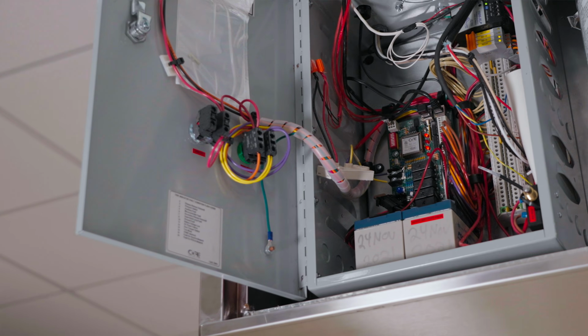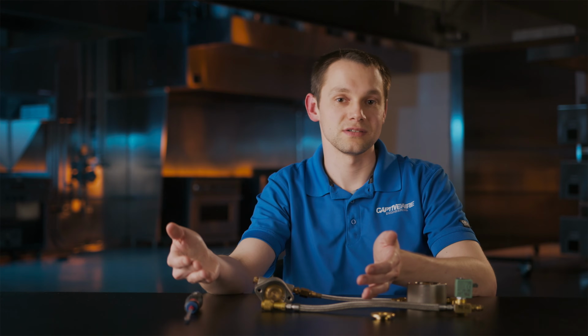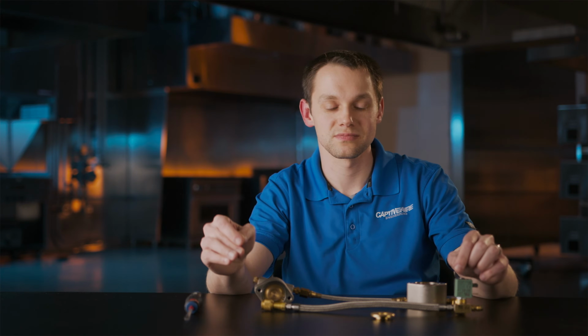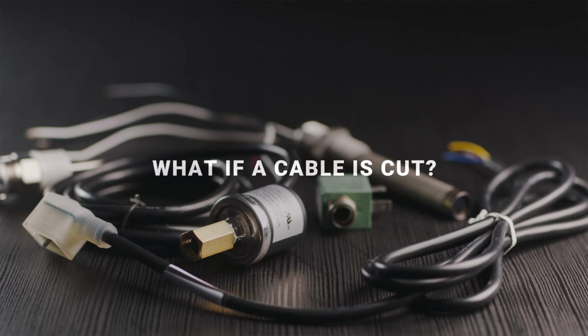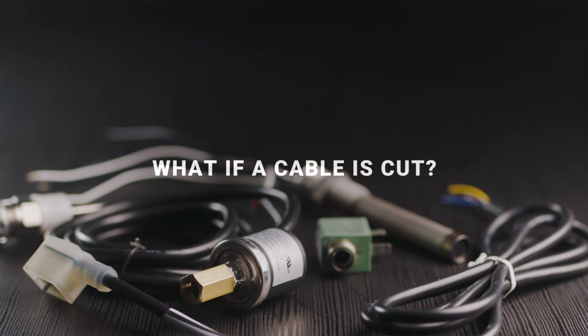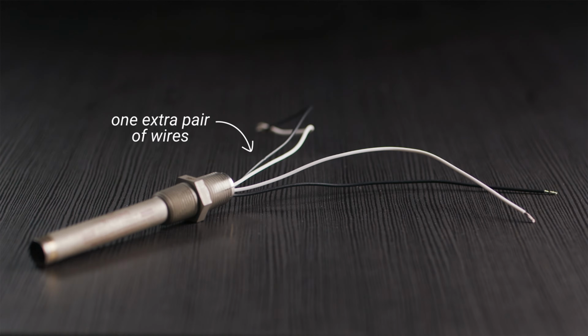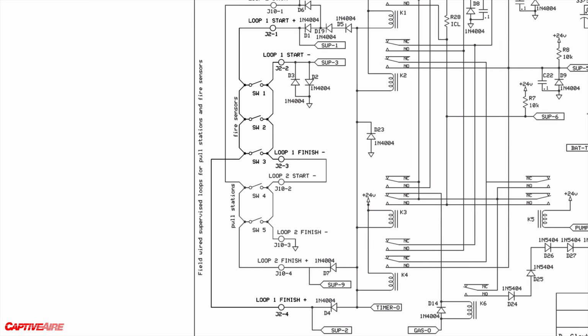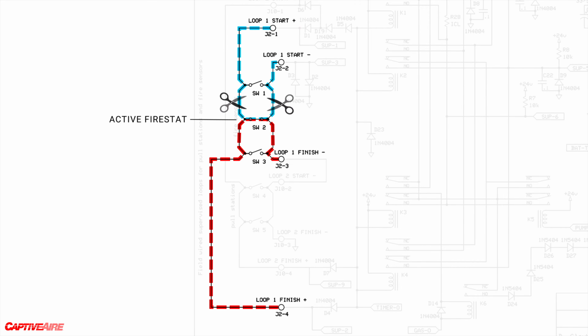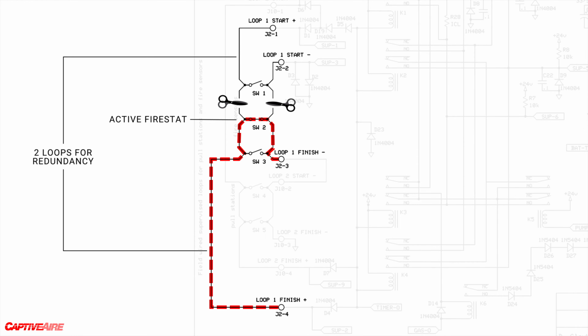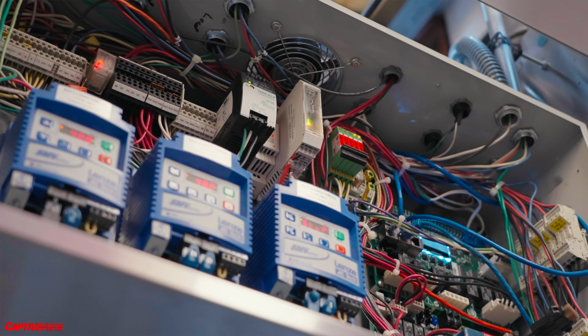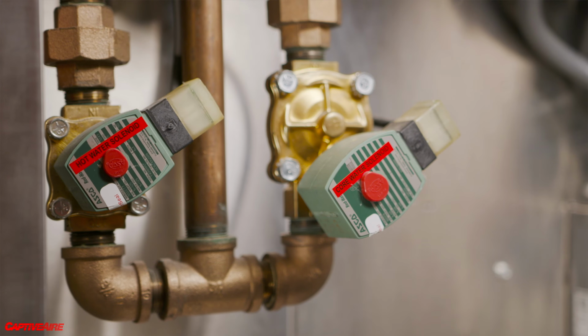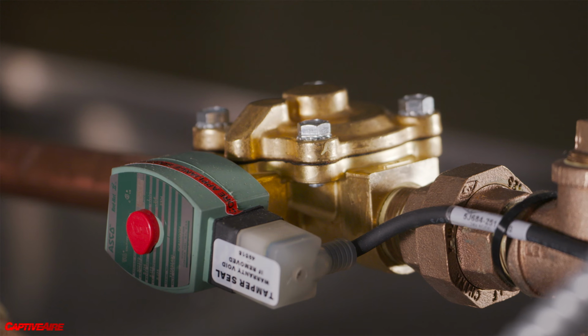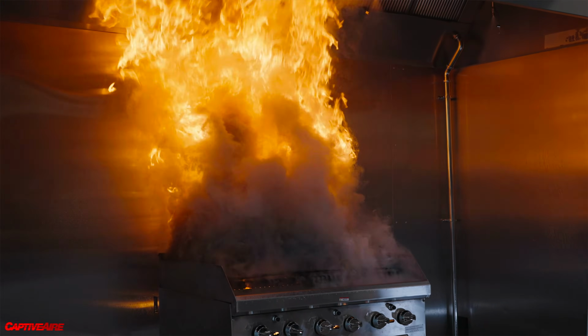The reality is we do have a battery backup system that even if there is a power outage, we'll have full capability of actuating that system and having everything safe. Okay, then what happens if a cable is accidentally cut or a component is faulty? With our fire stat, we implement a pair of redundant wires, and if you have fusible links, you just have one shot. If it breaks, it's literally not working. But even with our fire stat, if you cut up to 2 wires, this stat will still work. We can physically monitor the sensor to see if it's in good working order or not. So we are electronically monitoring all the sensors, the actuation devices, the key elements that will make sure that the system operates correctly in the time of a fire.